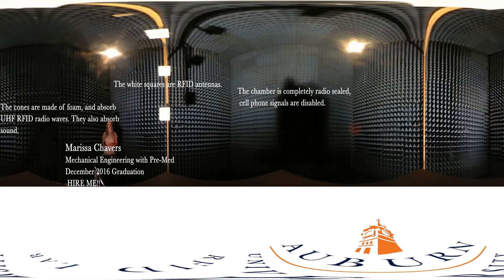It is 10 meters squared and covered in these specially designed cones to absorb radio waves in the 800 megahertz to 1 gigahertz frequency range. There are four antennas focused to the center of a rotating turntable that is used to test the products.